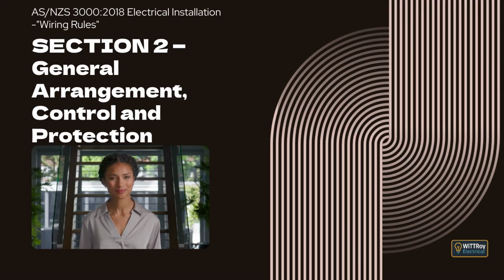Clause 2.5.5.2 Reduction of the probability of the initiation of a switchboard internal arcing fault. Switchboards rated at 800 amps or more per phase must be built with internal separation in line with ASNZS 61439.2.